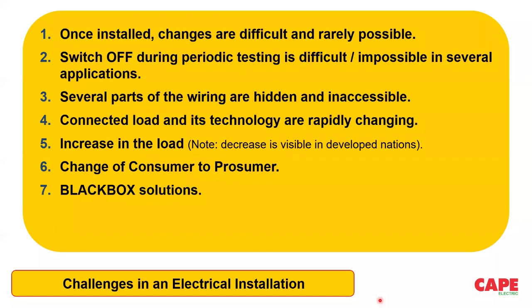Another challenge which we always face is the black box solution. What I mean by black box solution is, first we should understand that electrical safety is not a product which can be bought from the market. Like, I want 10 kgs of electrical safety, or I want 5 numbers of electrical safety. This is not a product which can be bought and installed in your system. And there is no one product available in the market which will make all your installation safe. If somebody says, I have a product which will make the entire installation safe, please note that this is almost impossible. Whereas in the market, you will get a lot of black box solutions which claim that my black box is the ultimate solution for all the daily problems faced in the electrical safety scenario.